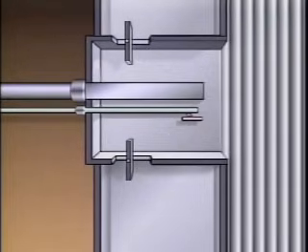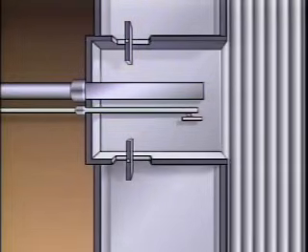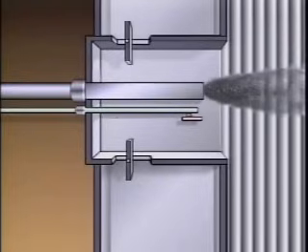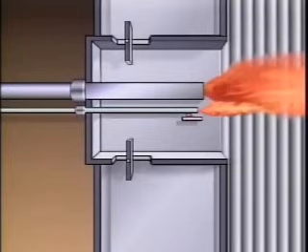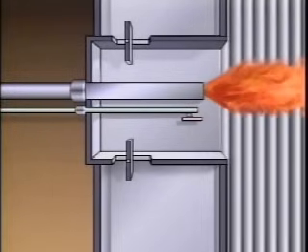A burner has three main parts: a fuel nozzle, an igniter, and one or more air registers. The fuel nozzle helps to create turbulence by spraying fuel into the boiler. The igniter provides the initial heat needed for combustion. After the fuel begins to burn, the heat needed to continue combustion is usually supplied by the flame in the boiler furnace, and the heat from the igniter is no longer needed.